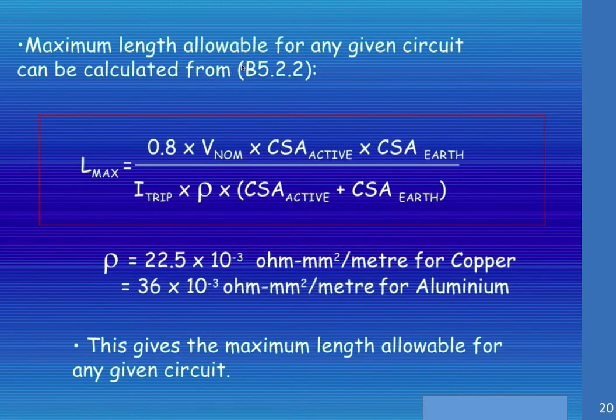The maximum allowable length for a given circuit can be calculated from table B5.2.2, and the formula may look involved but it's not that difficult. Our maximum length is 0.8 times the nominal voltage. There's our 80%, that 0.8 is our 80%. Multiply by the cross-sectional area of the active, multiply by the cross-sectional area of the earth.